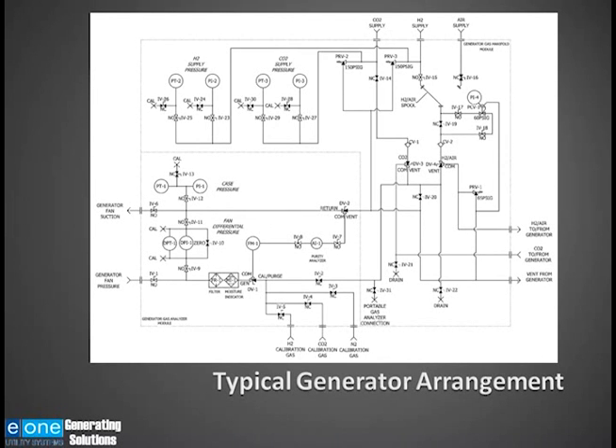Off on the left-hand side, you can see the 2 points where you're connecting the analyzer across the generator fan pressure and the generator fan suction. You also have a differential pressure indicator and transmitter across these 2 points. The transmitter sends the signal back to the control room, and the indicator gives you a local indication. You also have a point that's connected to the generator case so that you can monitor the case pressure and also send the signal back to the control room with a transmitter.